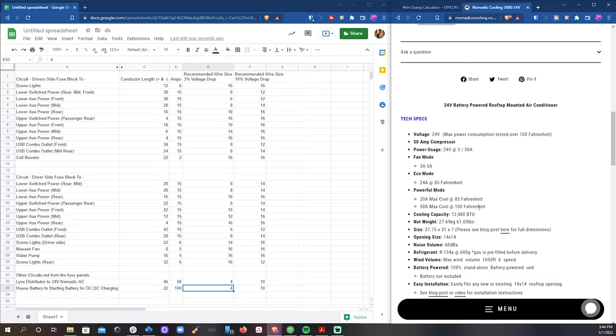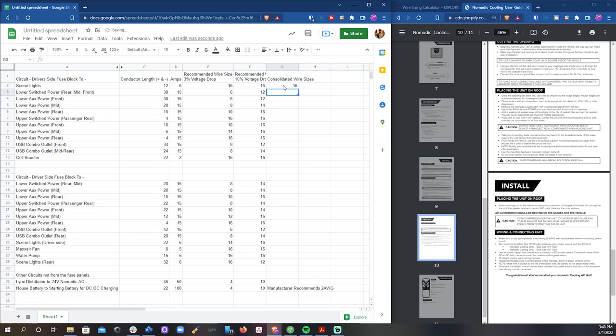Next I made another column for consolidated wire sizes, so that I could come up with a more concrete plan for the actual size of wire I was going to use. Now I wanted to err on the side closer to 3% voltage drop, just because it's always better to round wires to the next biggest wire size within reason.